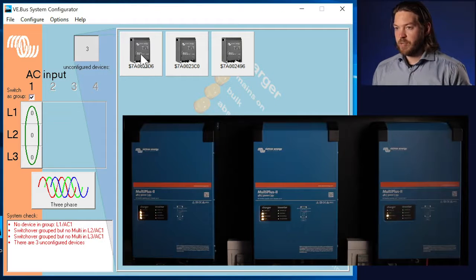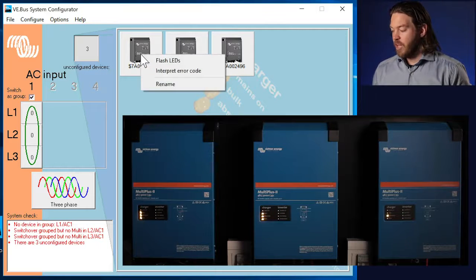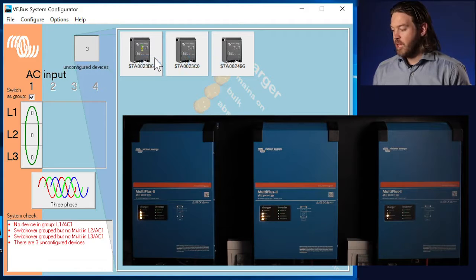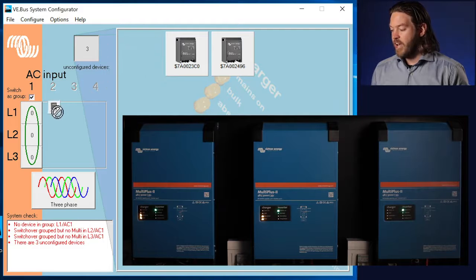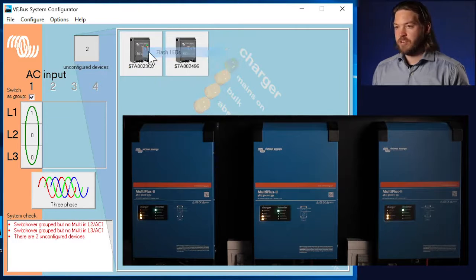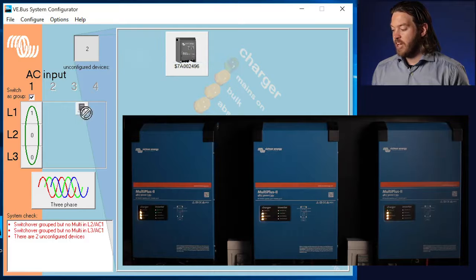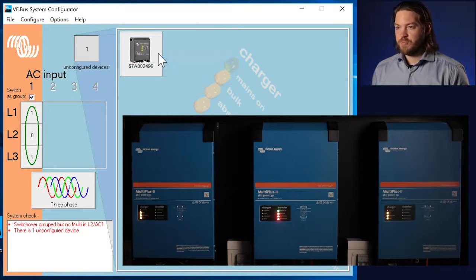So, to find out which unit's which, I'm going to right click on it. I want to select the first phase first. I'm going to click flash LEDs. Now, in this example, the first unit is the first unit, and you can see the LEDs flash. I'll stop flashing that, and then click the multi and drag it over to L1. I'll then right click on the second unit and flash its LEDs. In this case, it's the 3rd unit on the wall. So I'm going to stop flashing LEDs and drag it over to L3. Lastly, the only unit left, the unit in the middle.